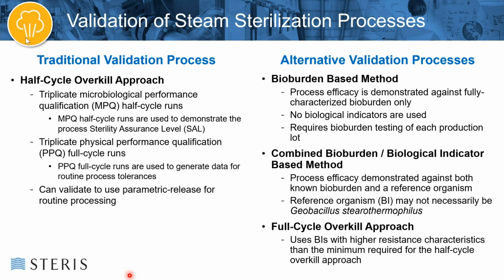I know that's a lot of information. I'm not going to get into a lot of detail on that right now because that's not the purpose of this presentation. But for the full cycle approach, if you have a BI that is substantially more resistant than 1.5 minutes, if we're talking about something in the range of 2 minutes, 2.5 minutes, or even 3 minutes to reduce that population by 1 log, then you can use that biological indicator and actually execute full cycles and not do these half cycles that a traditional approach would require.